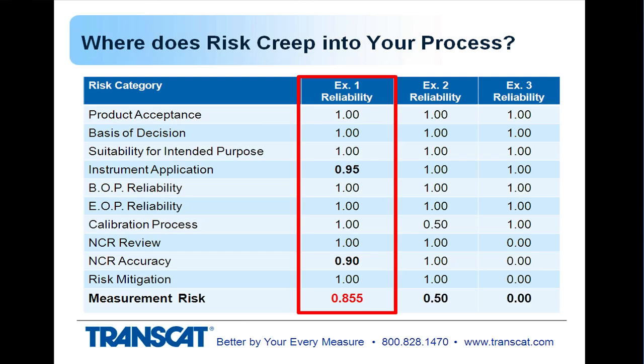For example, if all of the areas had a value of 1 assigned, but the instrument application indicates that in some situations it's being used incorrectly. You have the right instrument for the job, but there's something your personnel are doing in the process that causes errors, and you evaluate that this has a value of 0.95. And also that the accuracy or thoroughness of your nonconformance review afterwards, when you find out that you have an out-of-tolerance condition, isn't as thorough as it needs to be. Let's say you give that a value of 0.9. Your overall health would be 85 or 86%.